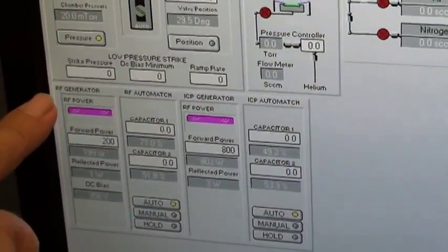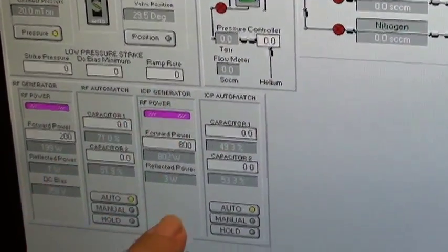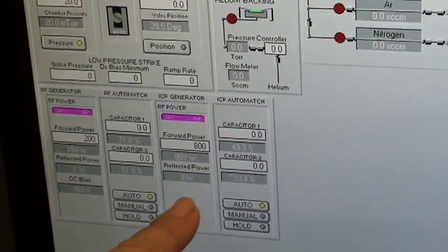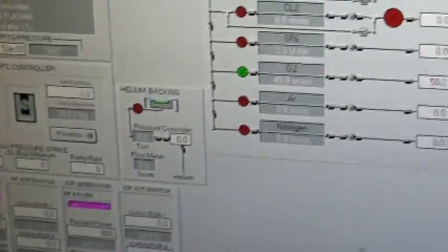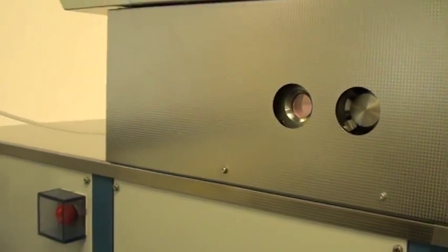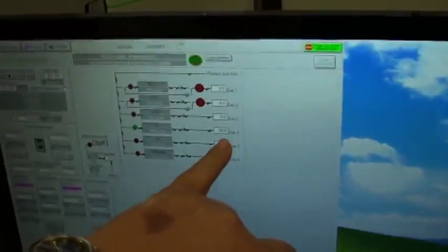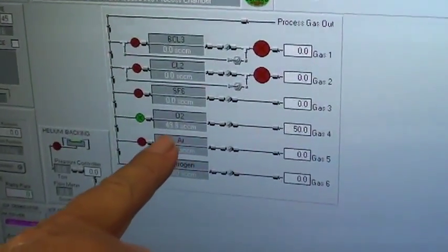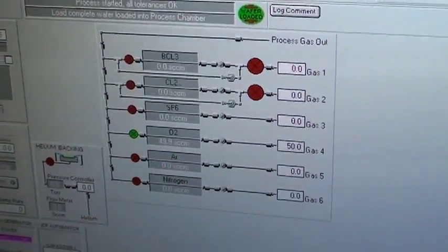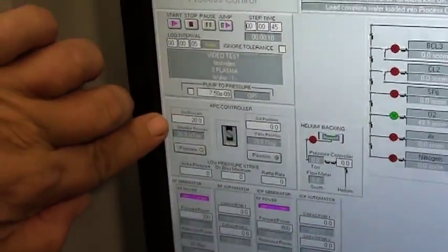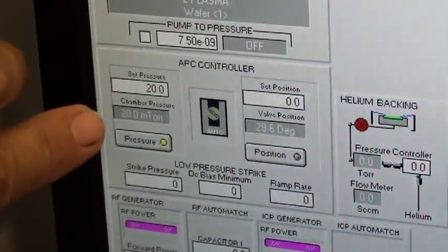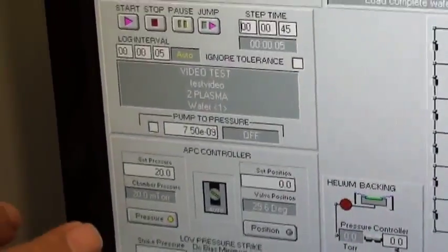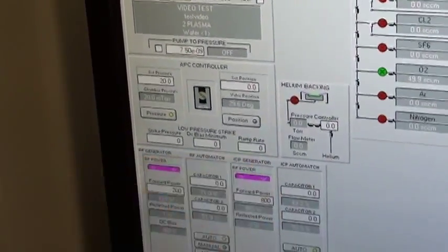We're running 200 watts on the platen. That's RF power, RF generator. ICP generator is the big one, and we're running 800 watts on the upper. We have a nice stable plasma in the chamber. Our set point is 50 SCCM for O2. We're running 49.950. 20 millitorr is our set point for pressure. We're running 20 millitorr. And we're running under pressure control. You can run under position control.